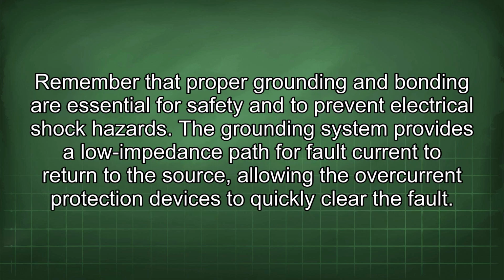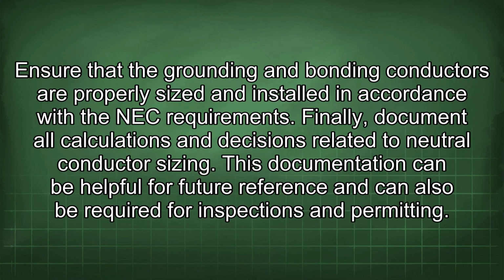Remember that proper grounding and bonding are essential for safety and to prevent electrical shock hazards. The grounding system provides a low impedance path for fault current to return to the source, allowing the overcurrent protection devices to quickly clear the fault. Ensure that the grounding and bonding conductors are properly sized and installed in accordance with the NEC requirements.